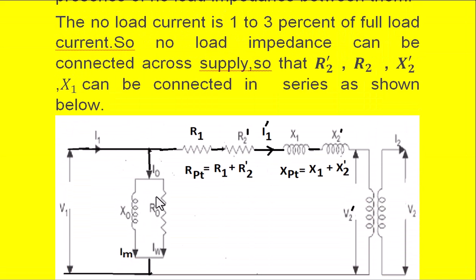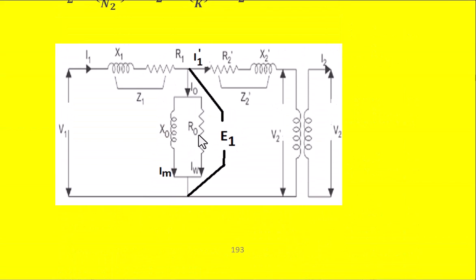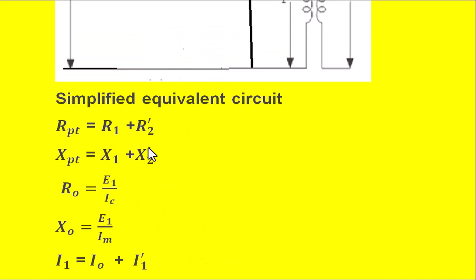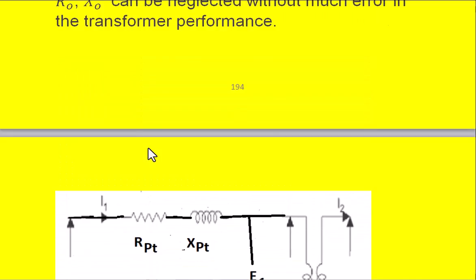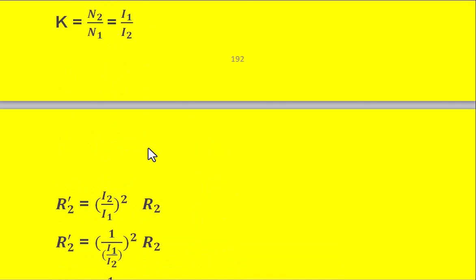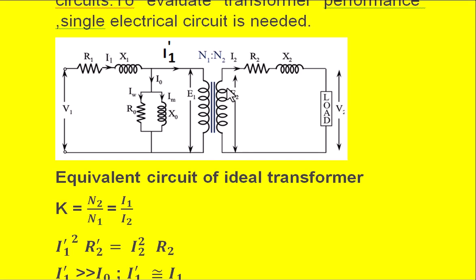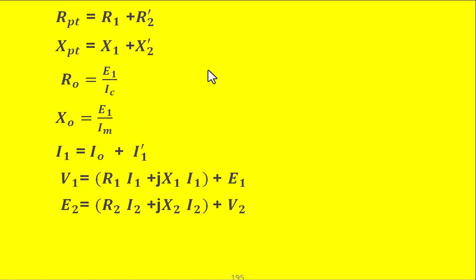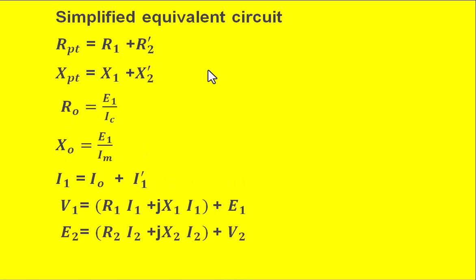Here Rpt equals R1 plus R2 dash and Xpt equals X1 plus X2 dash. R0 can be calculated as E1 divided by Ic, and X0 is calculated as E1 divided by Im. The input current to the transformer is I1 equals I0 plus I1 dash. So the equivalent circuit of the transformer referred to the primary is obtained by calculating R2 dash and X2 dash, which are the secondary winding parameters transferred to the primary side.